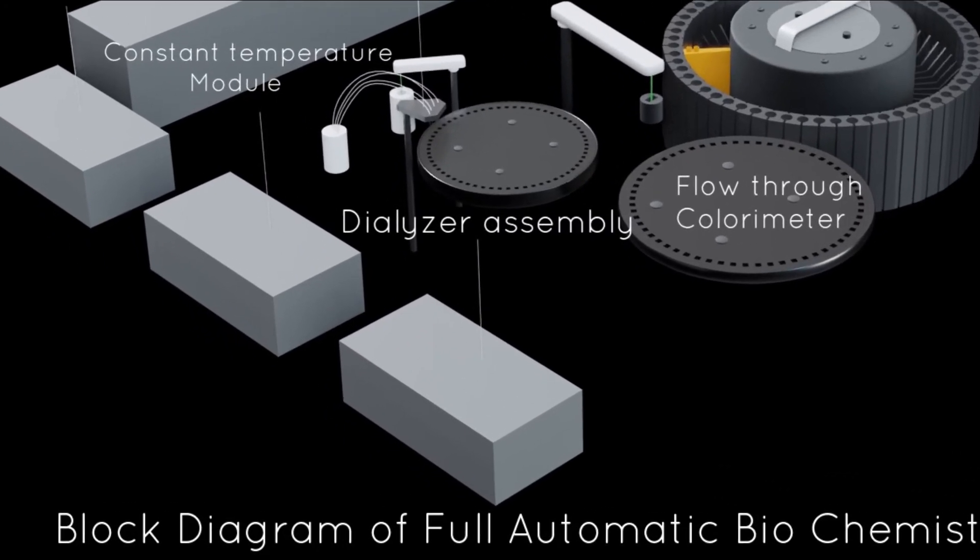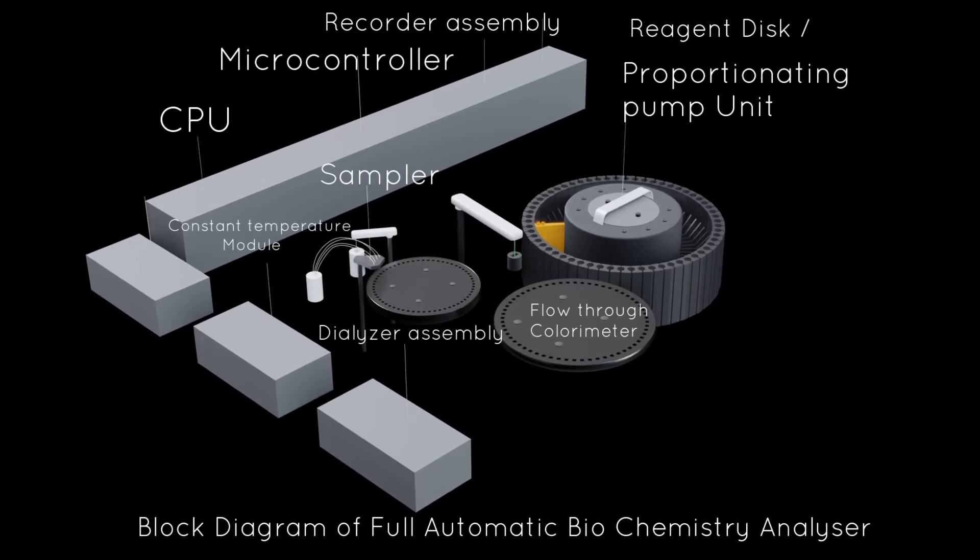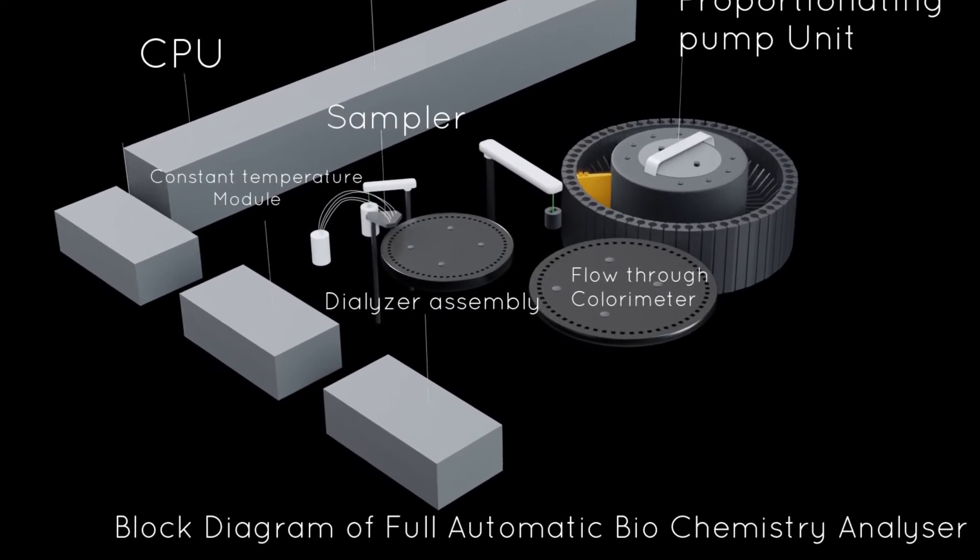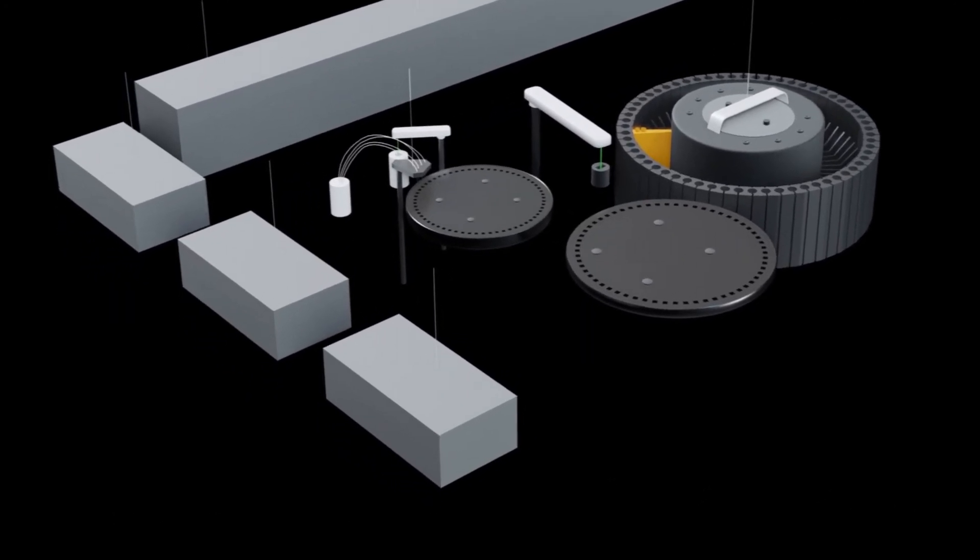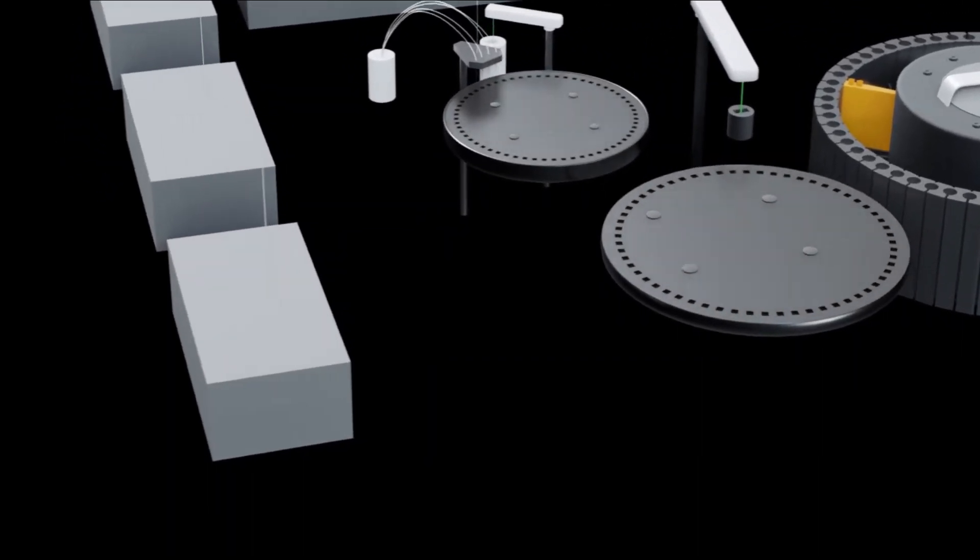It is important to ensure that the two streams flow in the same direction. Care must be taken to ensure that the output from the recipient stream is one which enters the remainder of the analytical system. If the sample stream is greatly diluted, the difference may not be seen easily.